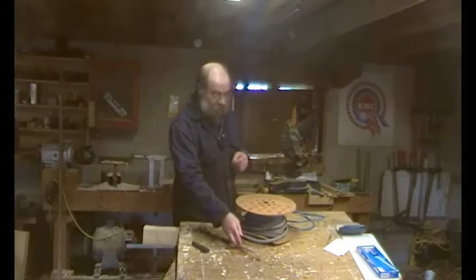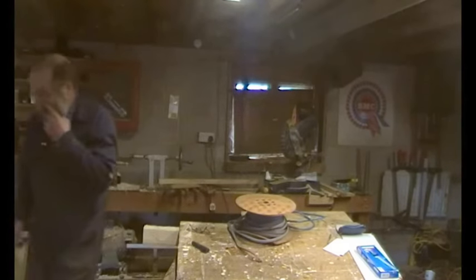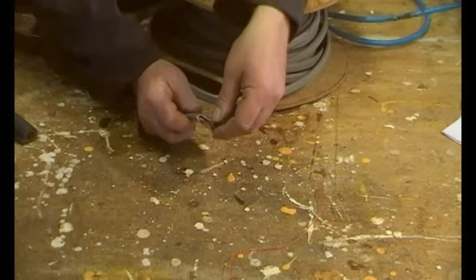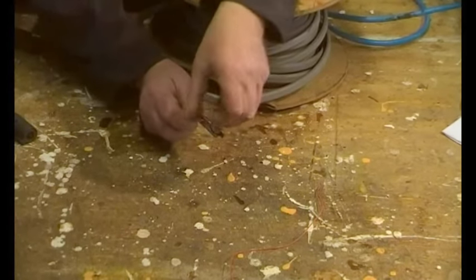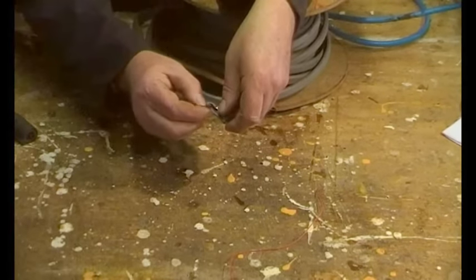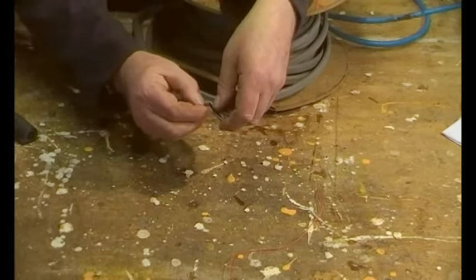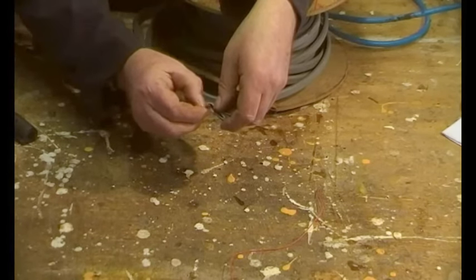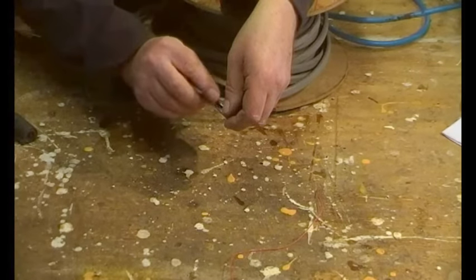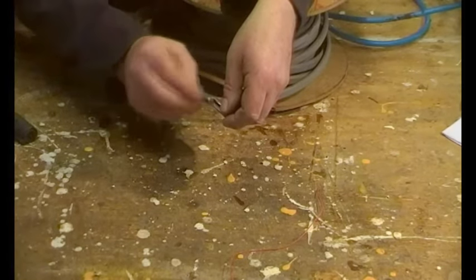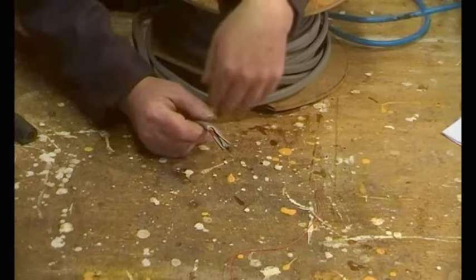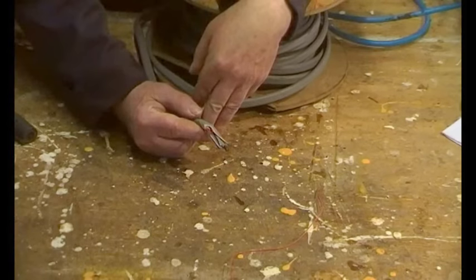The cable size is to do with the solid copper core, so it's the cross-sectional area of the copper. You can't just measure this because there are seven strands there and there's a load of gap between it. So you have to measure each individual strand and then do a bit of arithmetic.